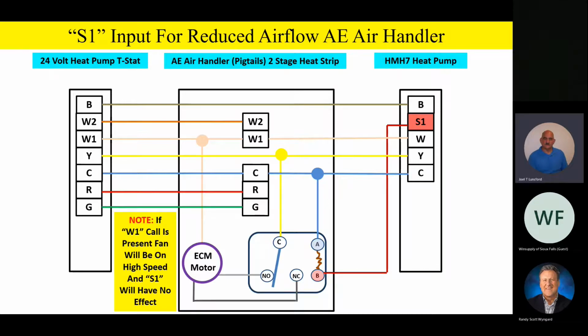Now remember, team, on an ECM type of motor or a variable speed motor, you can have multiple 24-volt inputs on those speed taps that won't hurt a thing. It won't burn anything up. Unlike a conventional motor, if you were to energize a capacitor-style motor on multiple speed taps, it'd burn the thing up. Well, these ECM high-efficiency motors, that doesn't happen. You can have multiple 24-volt commands on that motor at one time, and what will happen is it'll just drive that motor to the highest command that it's receiving.